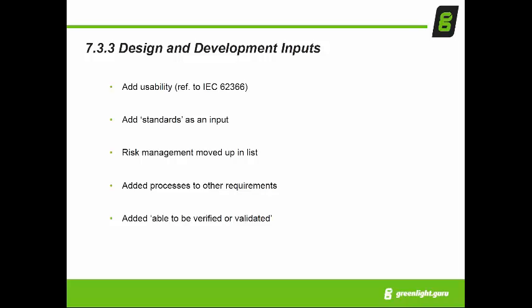It's happening again. There's an expectation in 13485:2016 that you're using your risk management process and your design and development process, that they're integrated together. There's an expectation that your risk management activities are feeding into your design and development efforts, and that you have specific design inputs and requirements that have been developed as a result of risk management. And this can be a really challenging thing to demonstrate and to prove, but that's becoming an expectation in ISO 13485:2016.